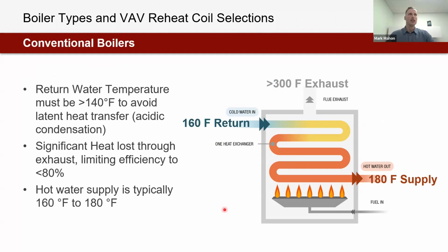150, of course, is possible as well. But what is very critical for a conventional boiler is the return water temperature must be greater than 140 degrees Fahrenheit to avoid latent heat transfer of the flue gas on the heat exchanger inside of the boiler. If we're going to start to see latent heat transfer and acidic condensation being generated within the boiler, that is going to actually be a huge risk for the boiler that could deteriorate and eat away at the metal that the boiler is made out of, because generally it's not made to be stainless steel corrosive resistant.